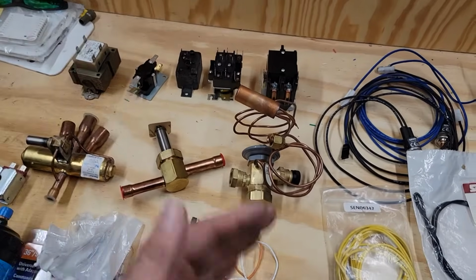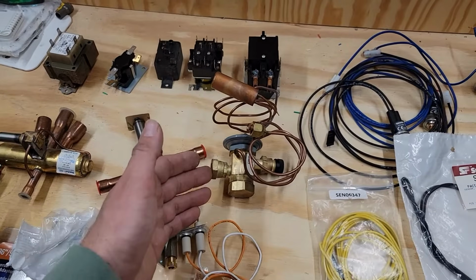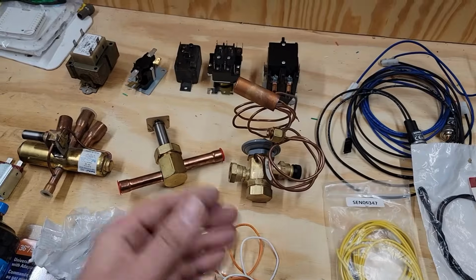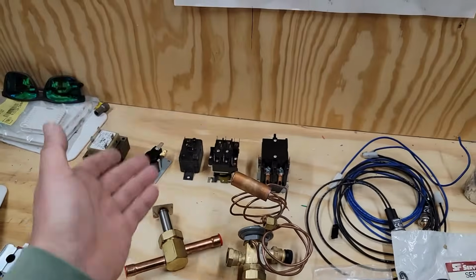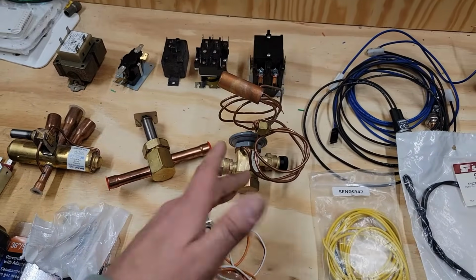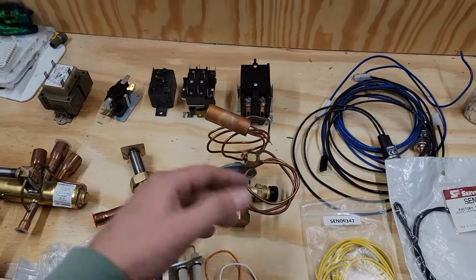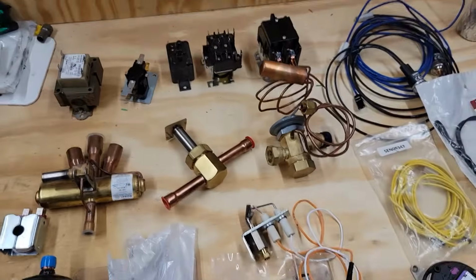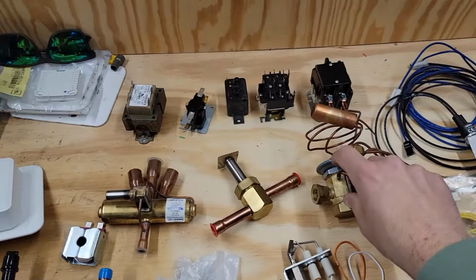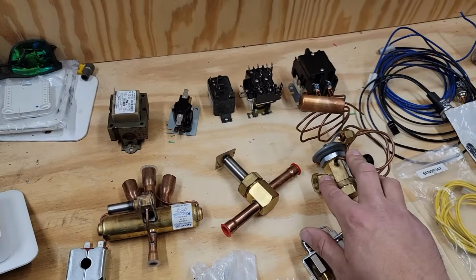The suction pressure can fall to 0, and when you try to add refrigerant, this thing is stuck closed, so you can't add refrigerant. Head pressure goes up to 500-600, and it doesn't matter if you recover refrigerant out of the unit, the head pressure is still super high. So check out my video on HVAC tips for technicians. I got a video on TXVs.